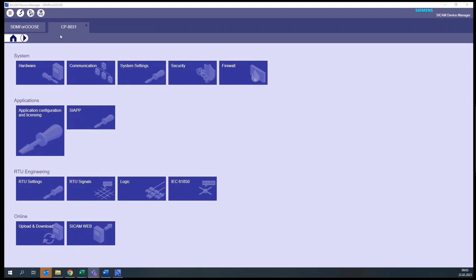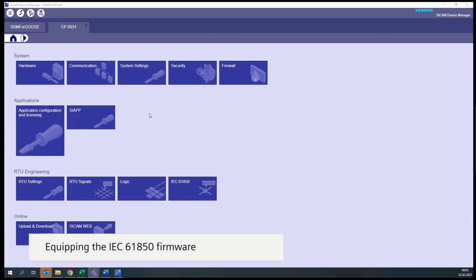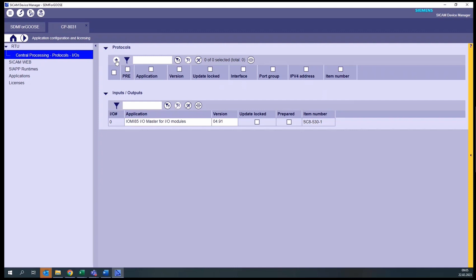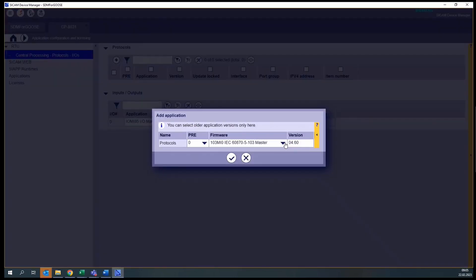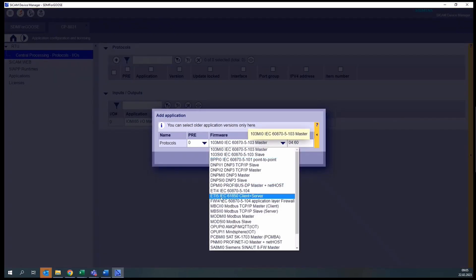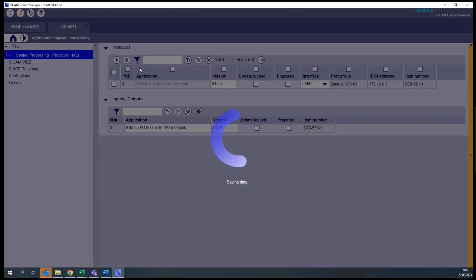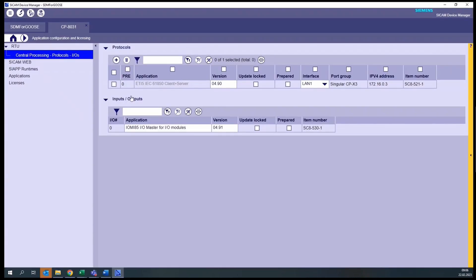Let's prepare this example for CP8031. First, we need to have at least one IEC 61850 firmware in the RTU. To do that, we click on the Application Configuration and Licensing box. Here we can add the protocol element for the IEC 61850 communication protocol, which for the Linux-based SICAM A8000 is the ETI5 firmware. Now we can see how the firmware has been equipped in the central processing protocols as protocol element 0.